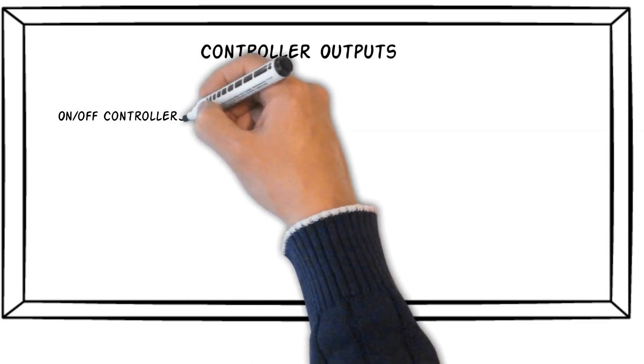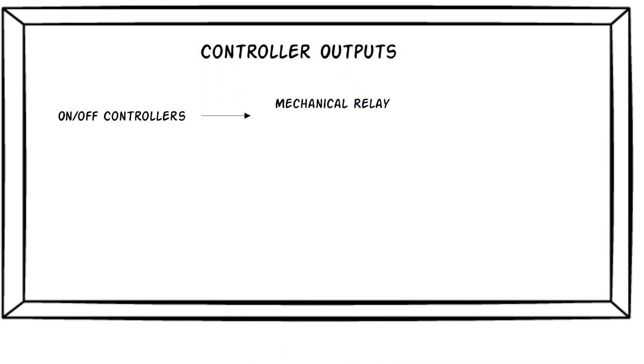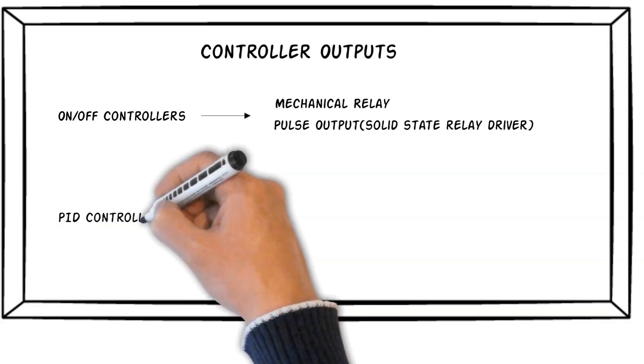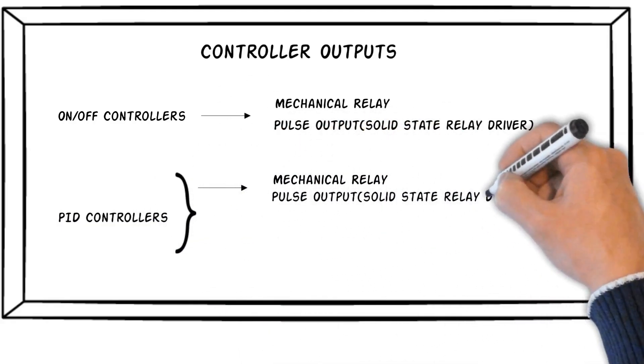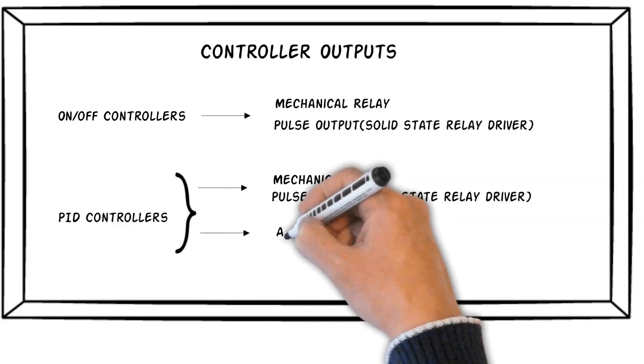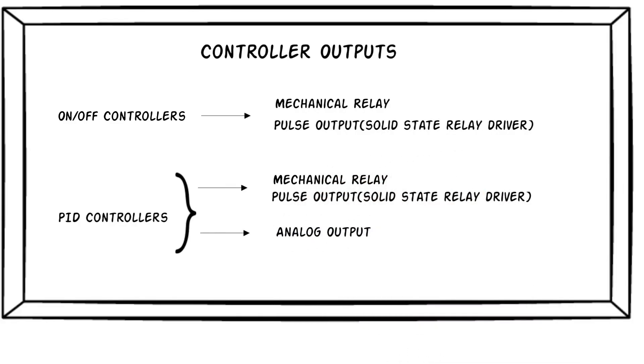On-off controllers have either a mechanical relay or a pulse output. The pulse output is sometimes called a solid-state relay driver because it's used to control an external solid-state relay. PID controllers are also available with relay and pulse outputs, but they may also have an analog output, which is typically 4 to 20 milliamps, 0 to 5 volts DC, or 0 to 10 volts DC.